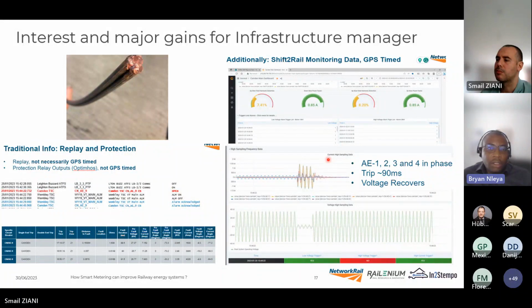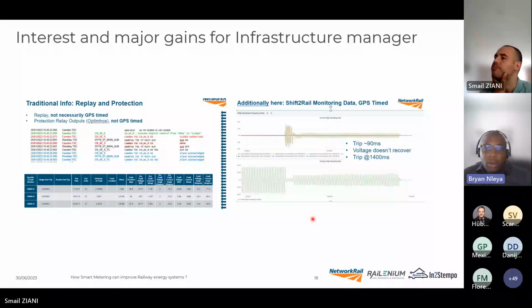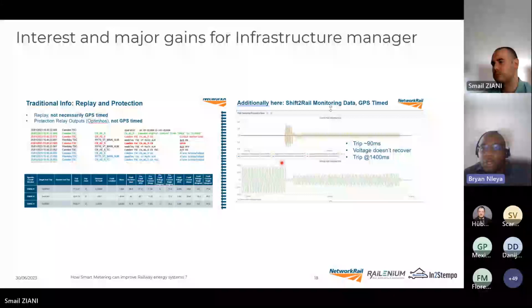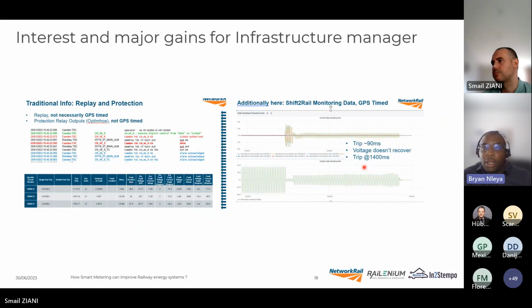On the next slide, you can see a recurrence at the same location after the circuit breaker had reclosed. The voltage after the protection system operated didn't recover—there was a sustained high impedance issue, which under normal circumstances, looking at the legacy information, would have been difficult to see. We can now explain that because of this sustained fault, combined with other issues we weren't aware of, there's an issue which explains why the catenary melted in the first place.